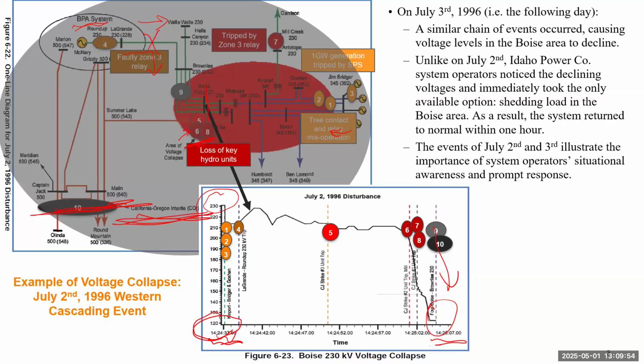But for this event, it takes much longer time. It's really a huge blackout in that area. So those 2 events, the first one is really a blackout. The second is a very good success story to save the system by noticing the potential voltage instability and taking some correction. But those 2 events show the importance of a system operator's situational awareness. If the operator knows what's happening on the system and takes some quick action, that can save the system, and can reduce a lot of loss.